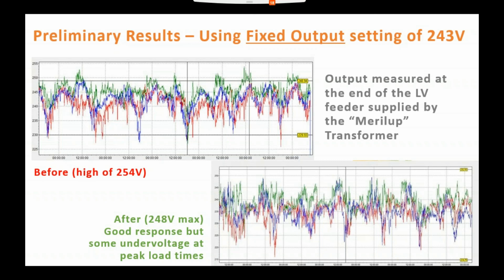So these are the loggers from the end of the feeder, and you can see under the before case we were getting some pretty high voltages, 254 volts. In this control system, which is a fixed output, we said no matter what happens on the supply side to the transformer on the MV, we just want you to keep the transformer voltage fixed at 243 volts. Even with that method, you can see that in the after situation we have a much better band of control, and voltages are hitting 248 max instead of 254. It is pretty good, but we are seeing some low voltage issues because WA has a very tight band, unfortunately.